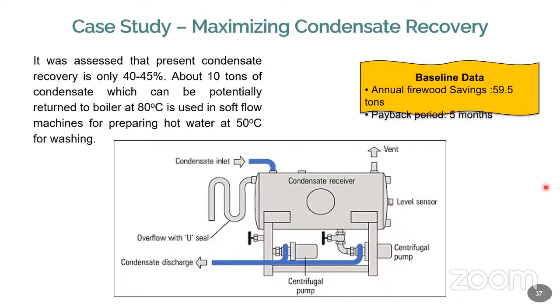and you need a separate tank for condensate water, which should be properly pumped to your feed water tank. Now this water is at a very high temperature, so the pumping system also must have proper high temperature materials. Otherwise the pump will fail. Insulation will fail, the piping system will fail. So automatically you need a very good steam recovery system.